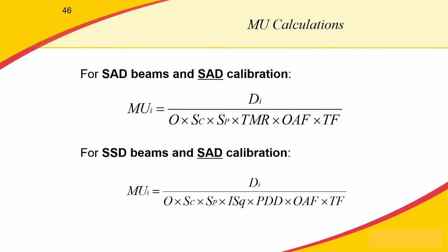Now let's say we wanted to calculate the number of monitor units that need to be delivered so we can deliver the prescription dose to the patient at the prescribed point. We use our dose calculation formalism and solve for monitor units: monitor units equal the prescription dose divided by our output calibration factor times all of the dose ratios needed to convert from the calibration condition to our specific treatment condition.